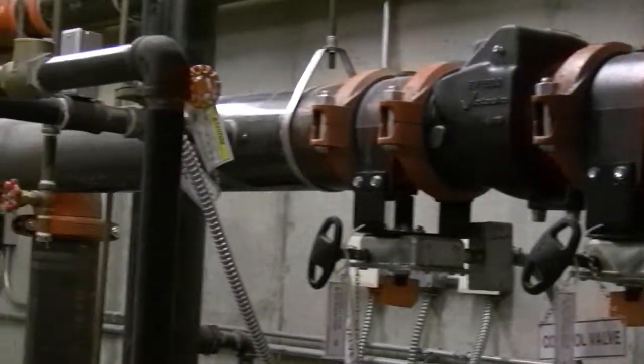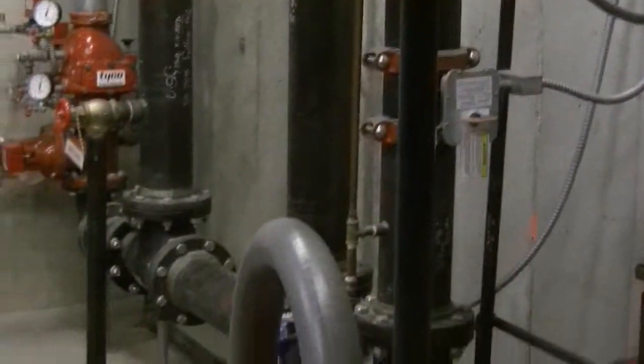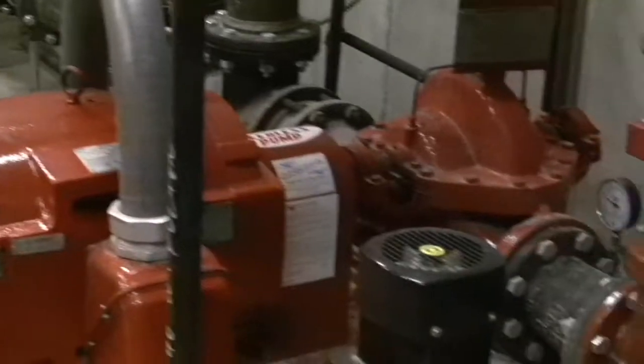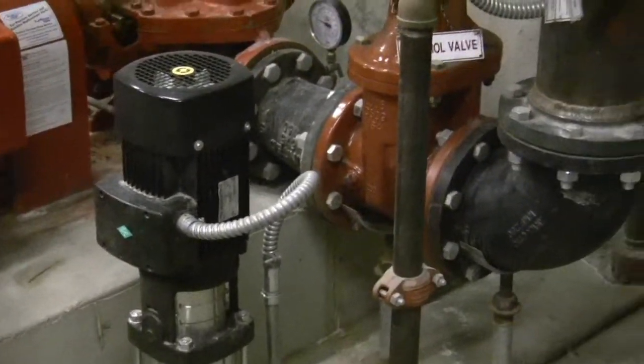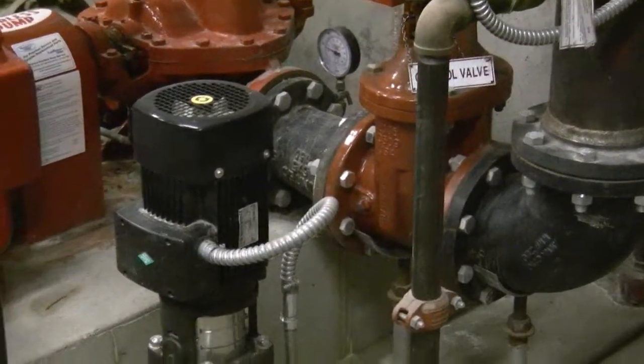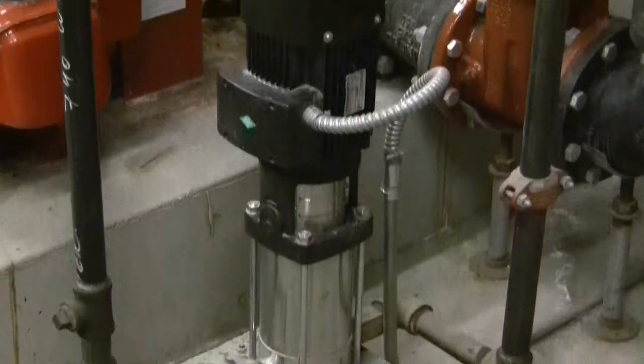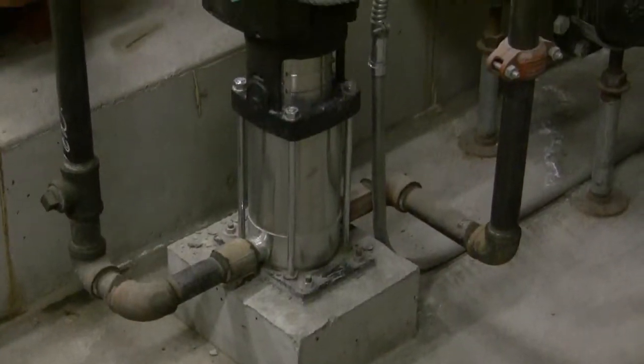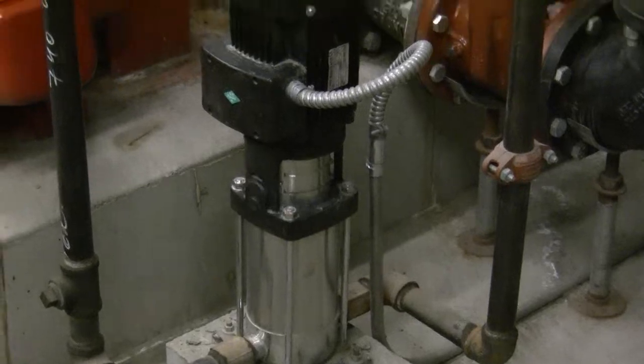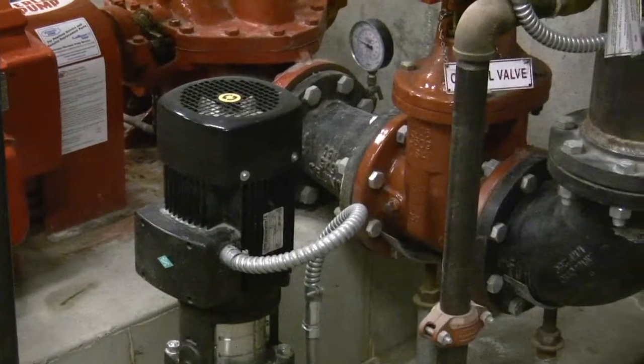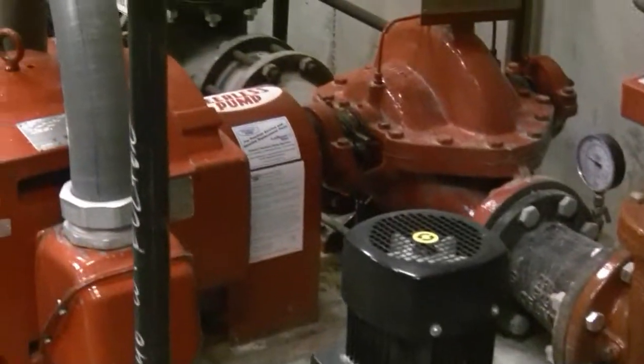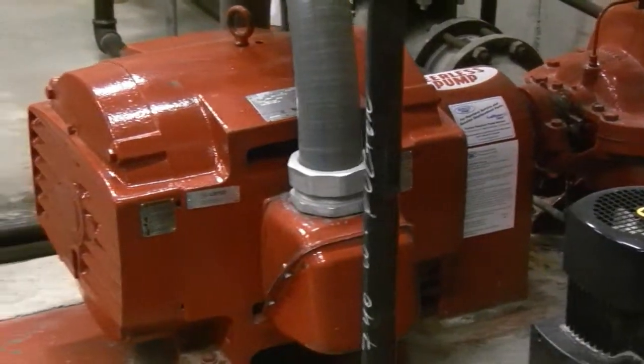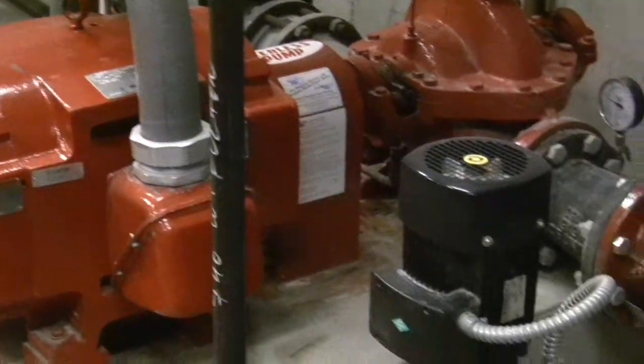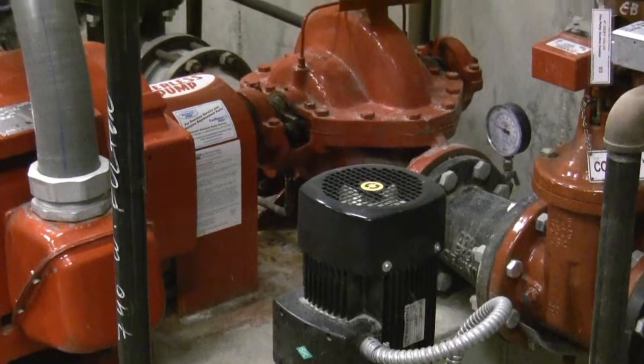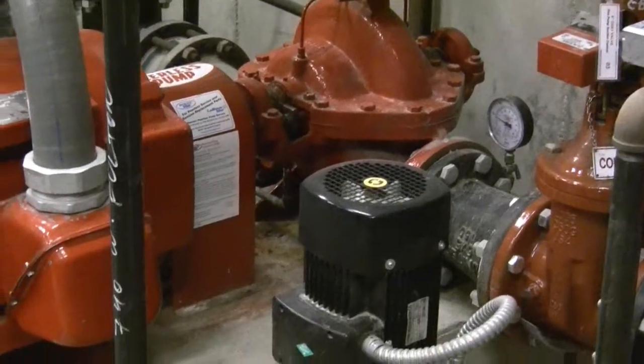Okay. We're now looking at the fire pump system, which consists of a large fire pump and a smaller jockey pump. The small jockey pump maintains pressure and takes care of small drops in pressure, which are not uncommon as the building goes from being warm to cold as water contracts. The jockey pump is activated by a drop in pressure. The larger pump is activated by a drop in pressure beyond what the jockey pump can hold.